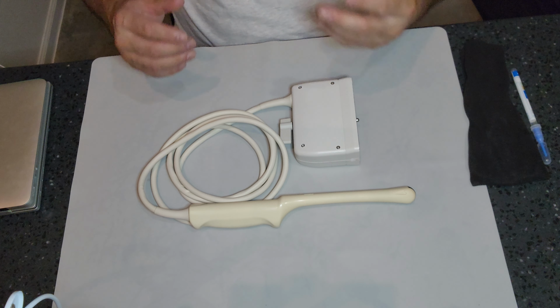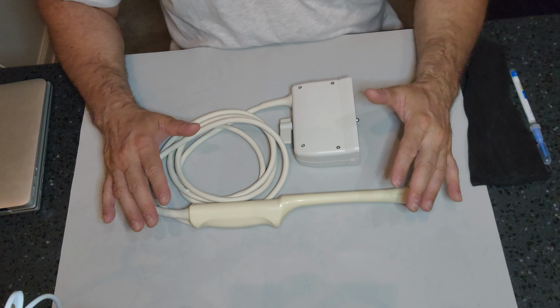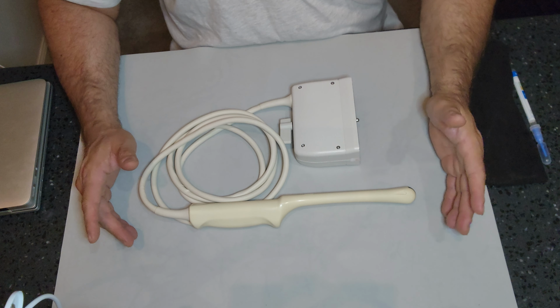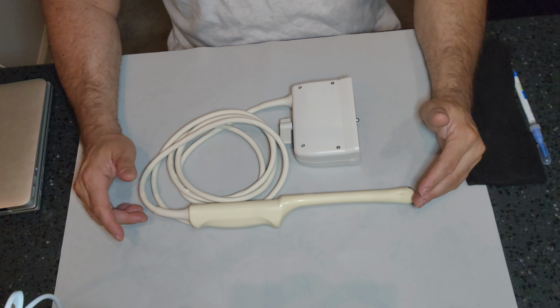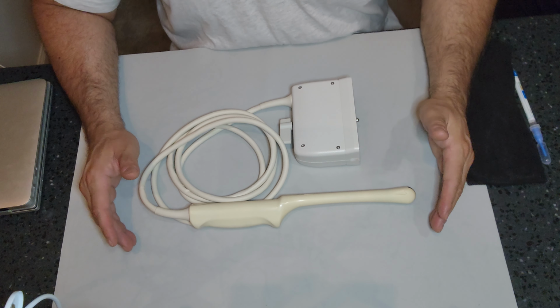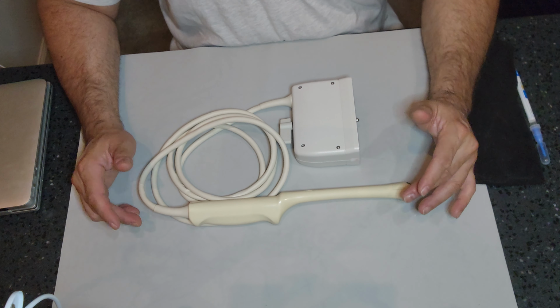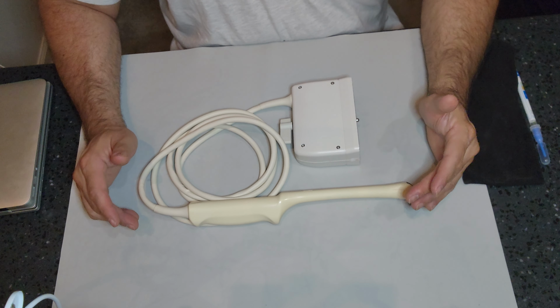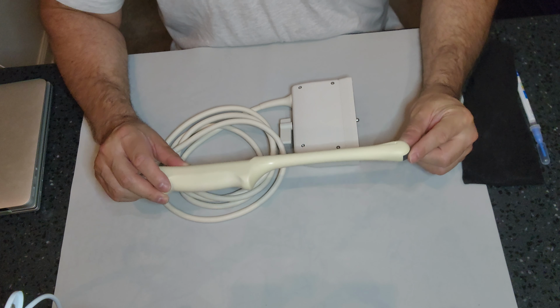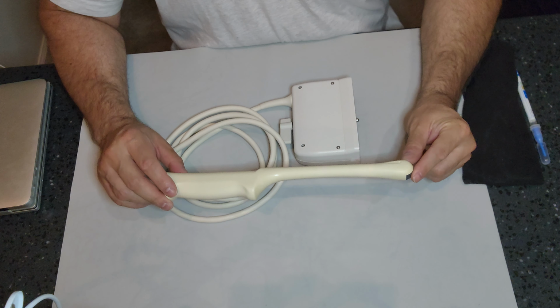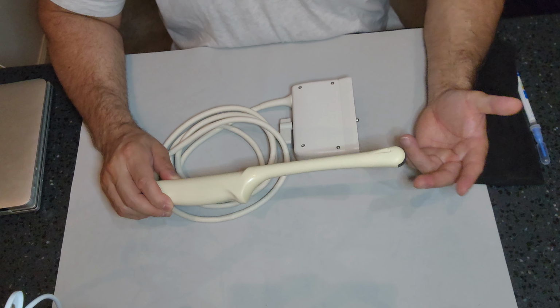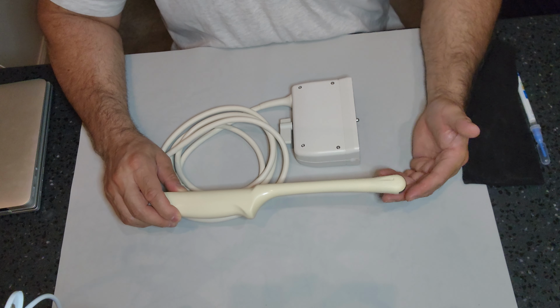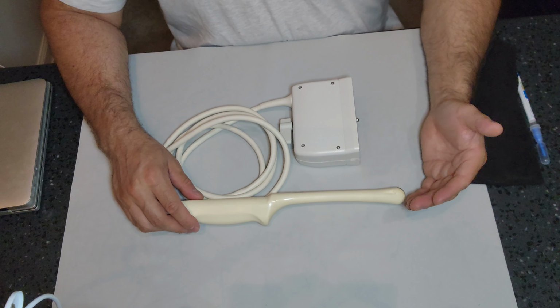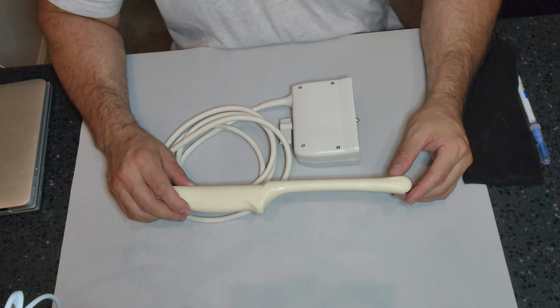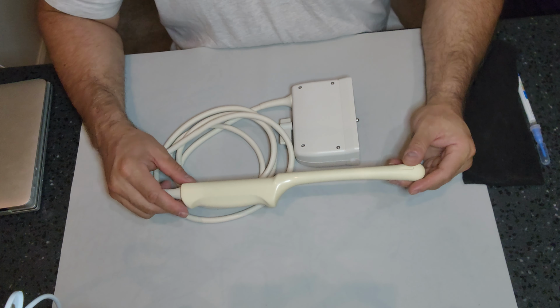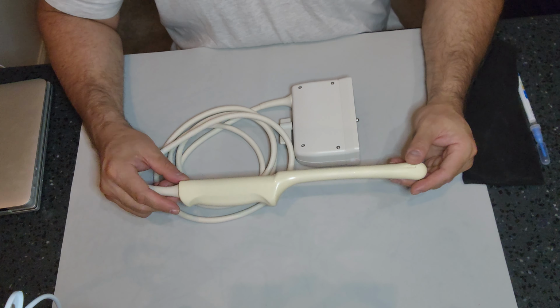But again, we want to know, what is the use of the probe? So the Spaulding classification system is going to guide us, okay? But again, what's the policy of your facility? What are you doing with it? If the IFU states that the device can withstand high-level disinfection, but only requires low-level or intermediate disinfection, is your policy saying, you know something, we're going to go on the safer side and high-level disinfect it? Or can you high-level disinfect it and it gives you a sterilization option?